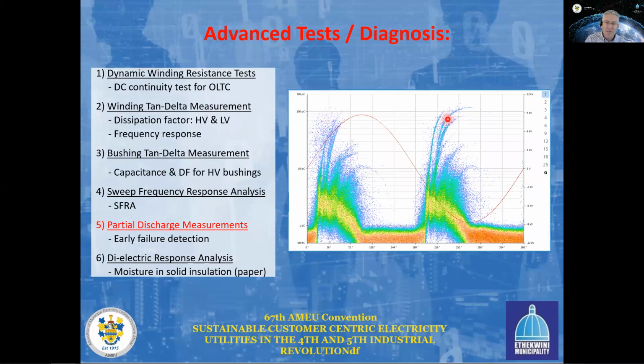And if the level of this partial discharge that we see here increases, that is an indicator that the discharges are increasing and obviously that the insulation is deteriorating. And this could be an early indicator that our transformer is deteriorating and the insulation is deteriorating, meaning that it could fail into the future.